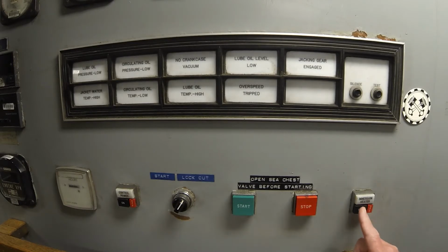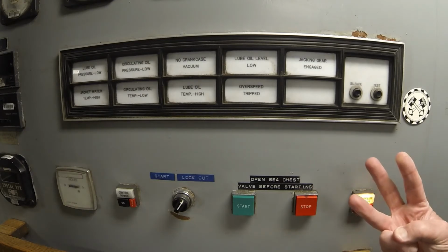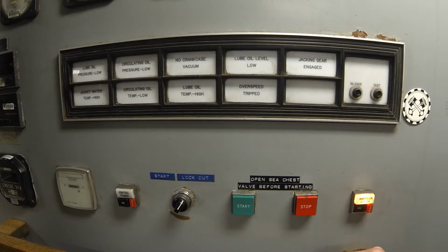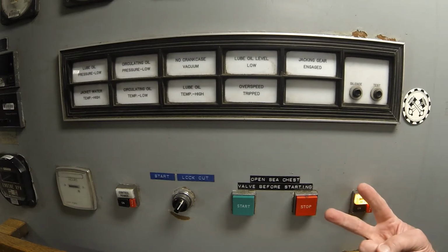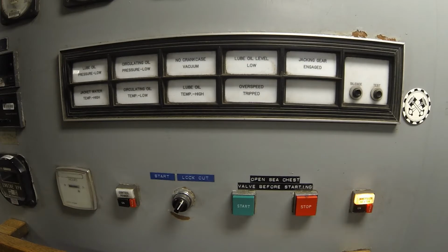When I energize the immersion heater, I'm activating 3 circuits. One is a circulating lube oil pump, which is circulating oil through the engine. It is a positive displacement rotary gear pump with an electric motor. The second circuit I'm energizing is a circulating jacket water pump, which is a centrifugal pump. And the third circuit is the immersion heater element, which is heating the water as it travels through the circuit.